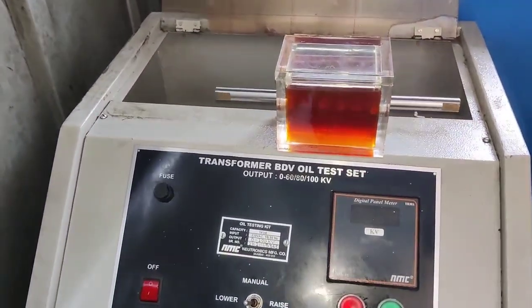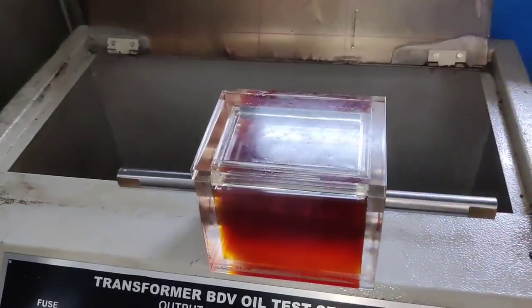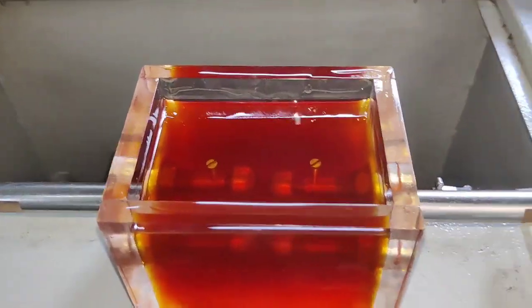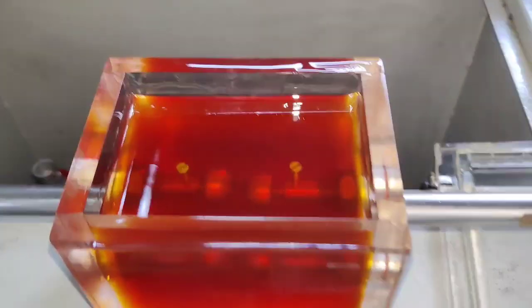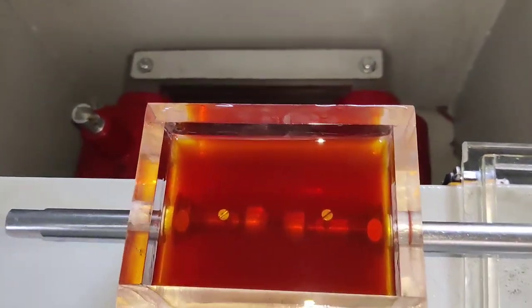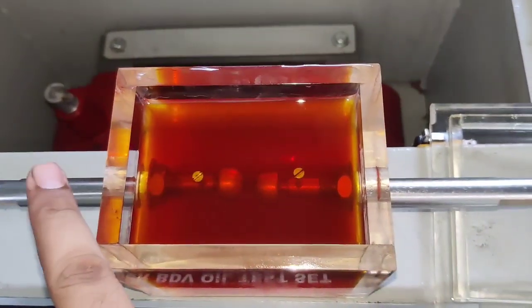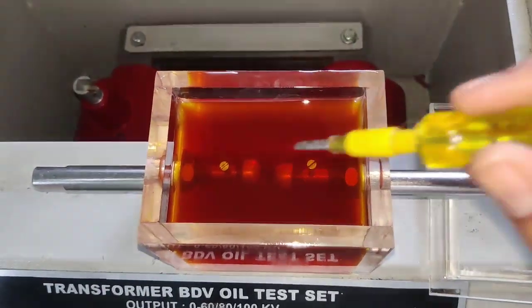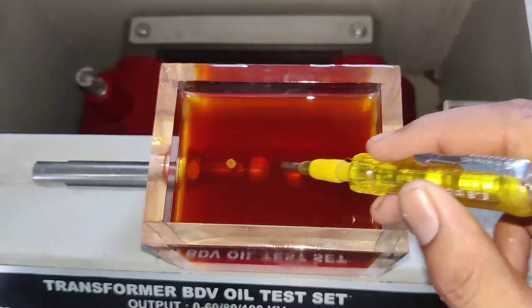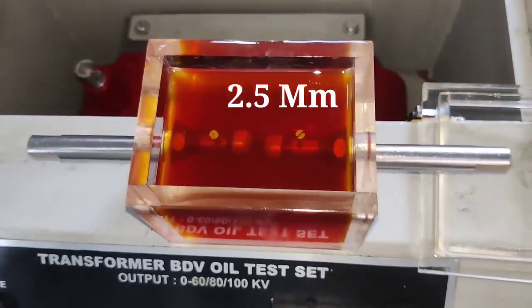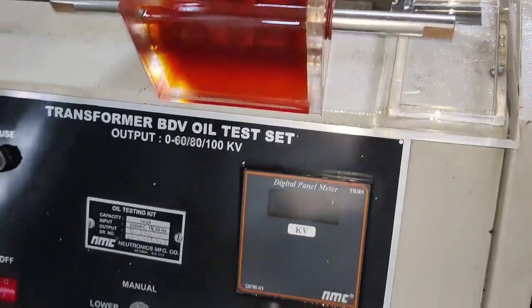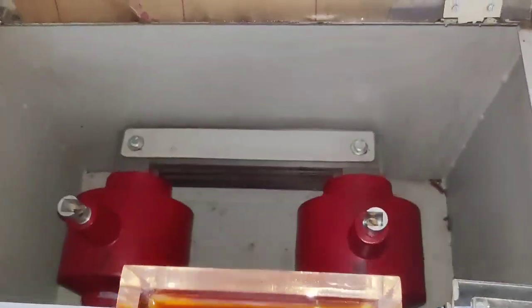First, you need to take transformer oil in this container. We have already taken transformer oil in this container. You can see here, in this container we have two electrodes, the first electrode and the second electrode, and the distance between both electrodes is 2.5 mm. Between them, a high electric voltage in kilovolts is generated.